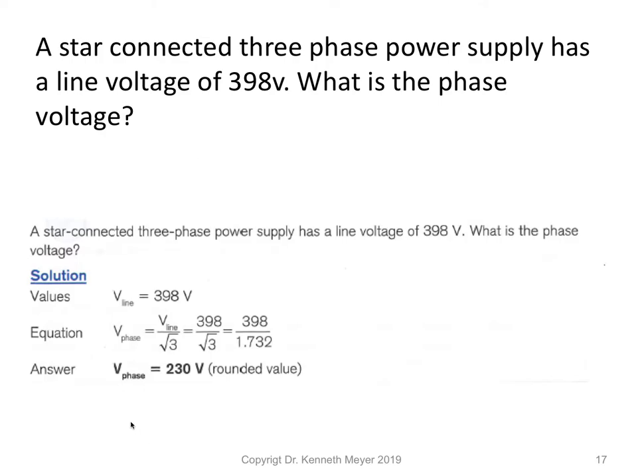Quick example: a star-connected three-phase power supply has a line voltage of 398 volts. What is the phase voltage? We know V_phase = V_line ÷ √3, so 398 ÷ √3 = 398 ÷ 1.732 = 230 volts. Very similar to the kinds of values we've already been looking at.